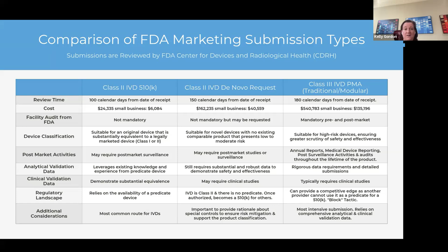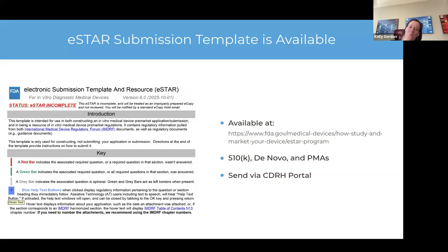There are templates now, so it's very nice because you know what's expected. If you are thinking about bringing your product through FDA as a class 2 or class 3, I recommend looking at these templates, thinking with the end in mind, where you see everything that's required from FDA, and you can submit it through their portal. CDRH was pretty slow at becoming electronic, so these submissions are still voluntary for PMAs, but I highly recommend using the templates because at least you know what needs to be in there. They can break sometimes, especially with interactive reviews, so sometimes you want to work offline in all your documents and pull it into the templates.